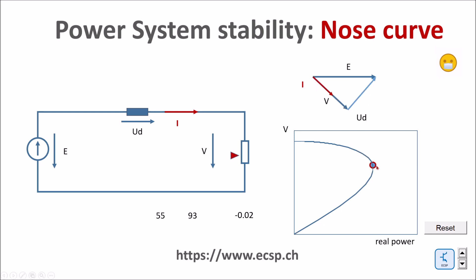Here I am now on the no return point. This is the point where I will lose stability because I can evacuate less electrical power than I feed mechanical power into the generation.